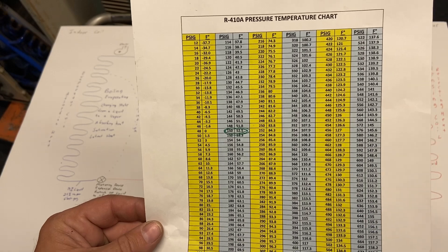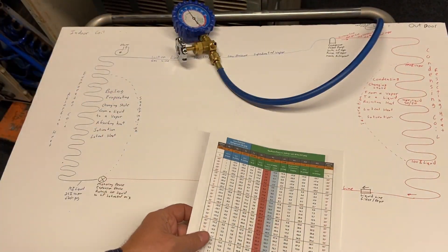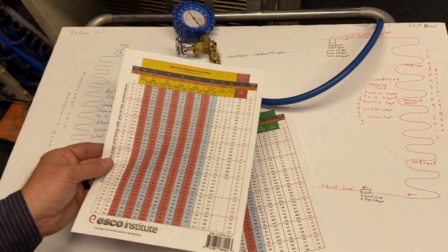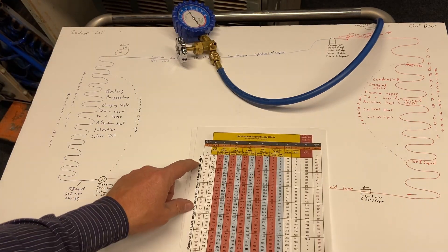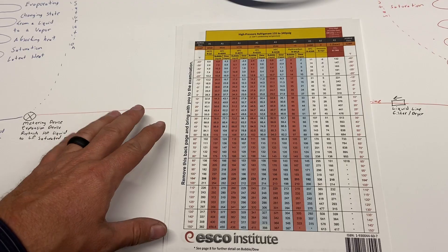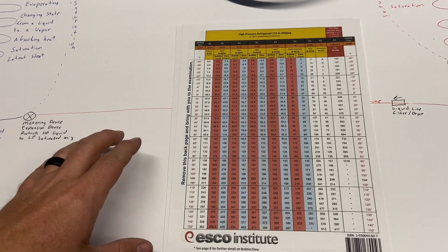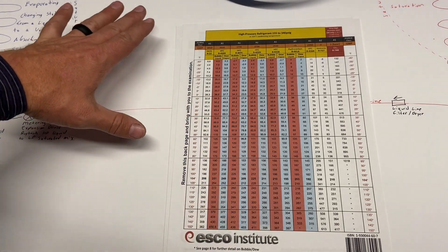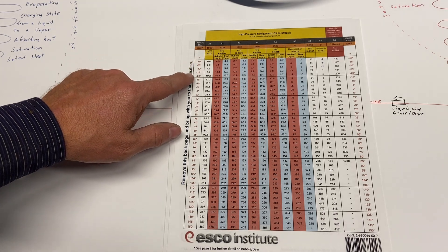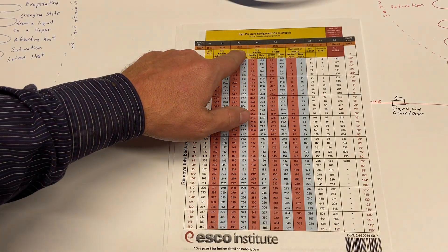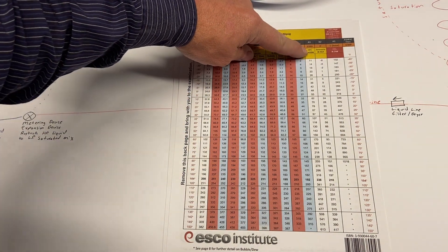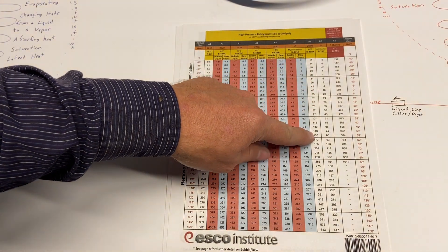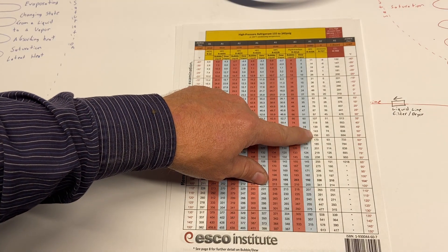This helps get your mind around it, but in reality the temperature-pressure charts you'll encounter are a little bit different — they have multiple different refrigerants. This one is available from the ESCO Institute, which is one of the testing organizations for the EPA test. I like their chart because it has a ton of information and is simple to find. On this side we have temperature in degrees Fahrenheit, and across the top are all the different refrigerants. The refrigerant we're working with is R410A, so I'll scroll down to find 150 PSIG.